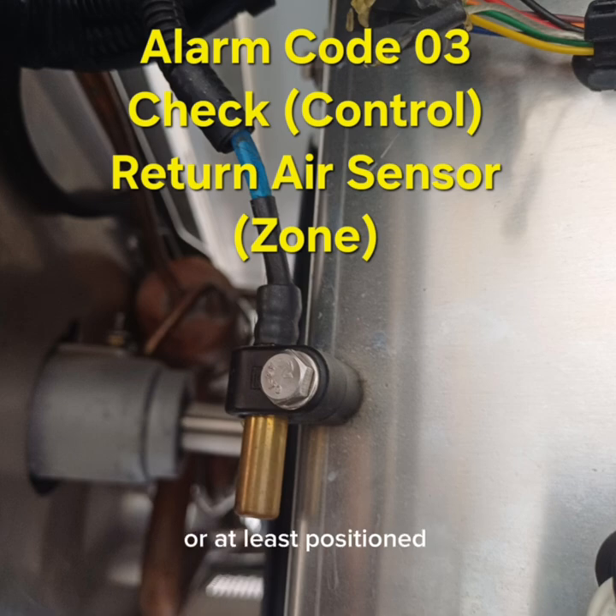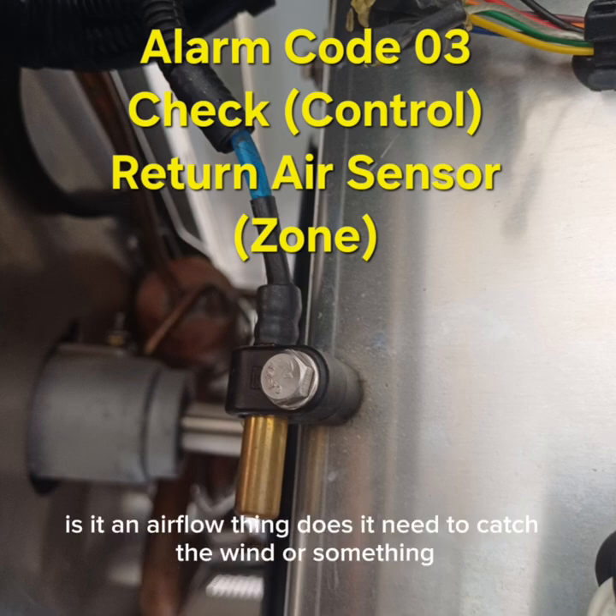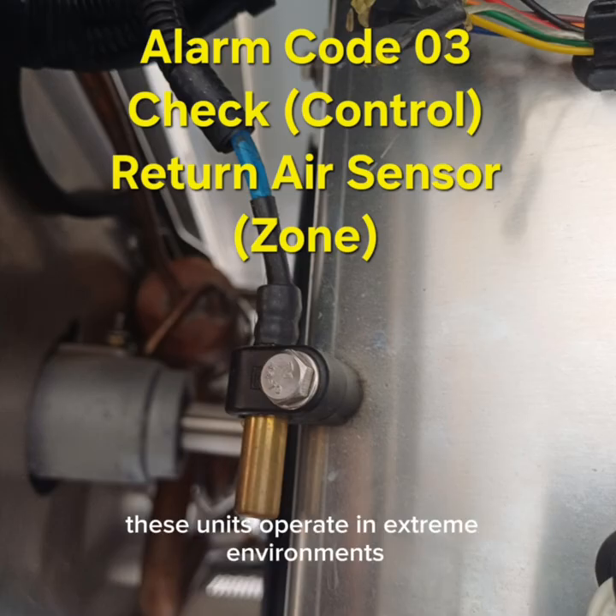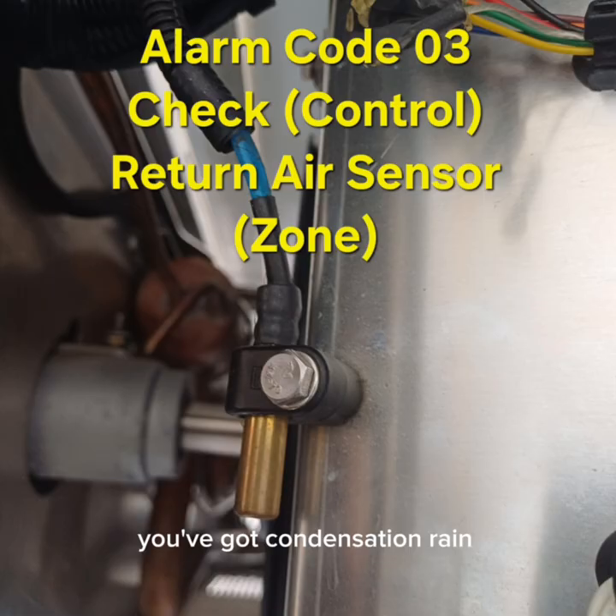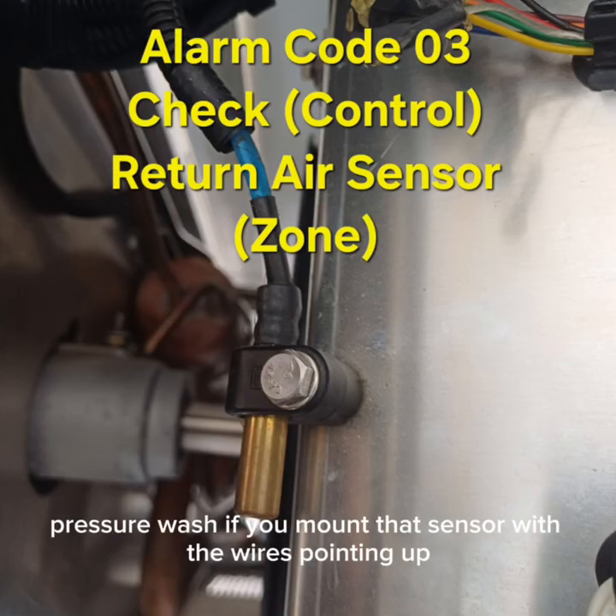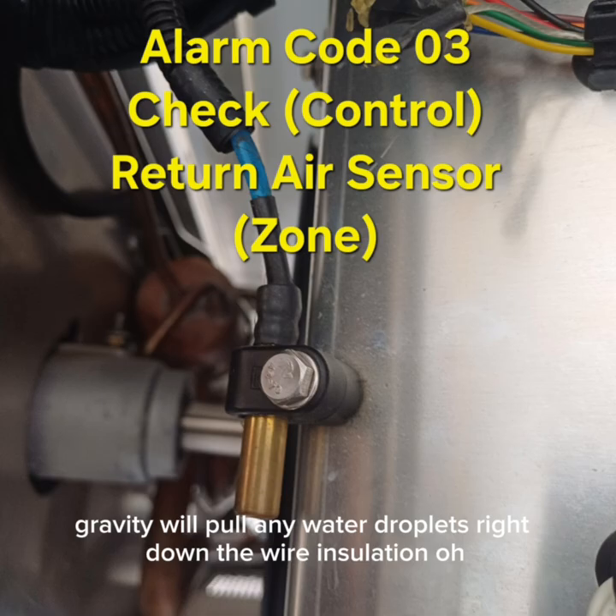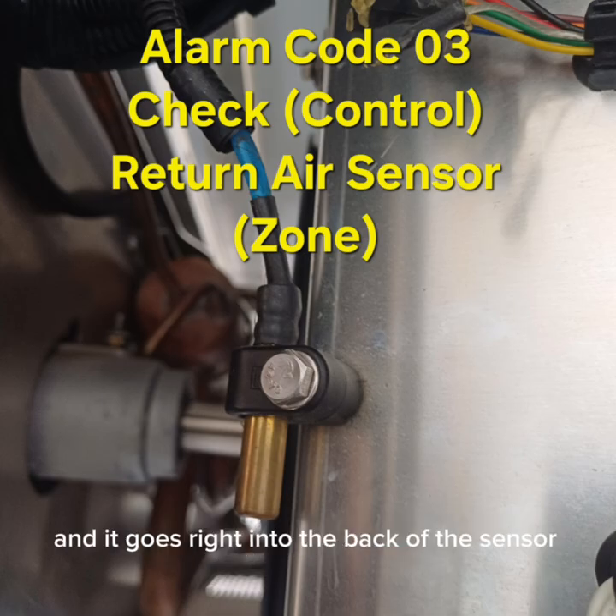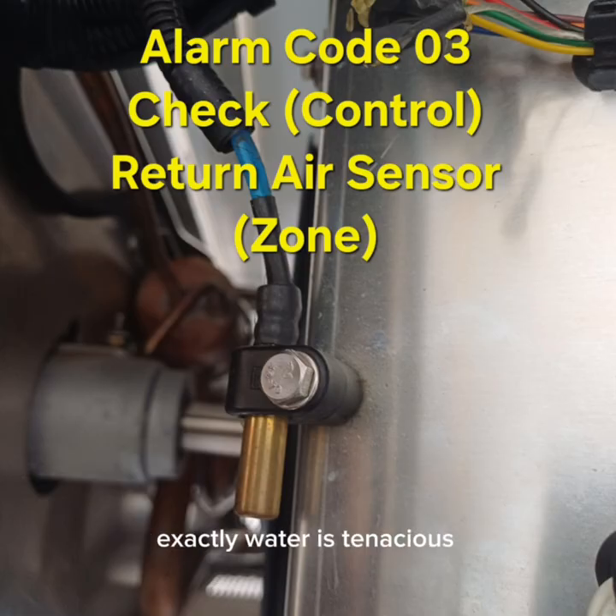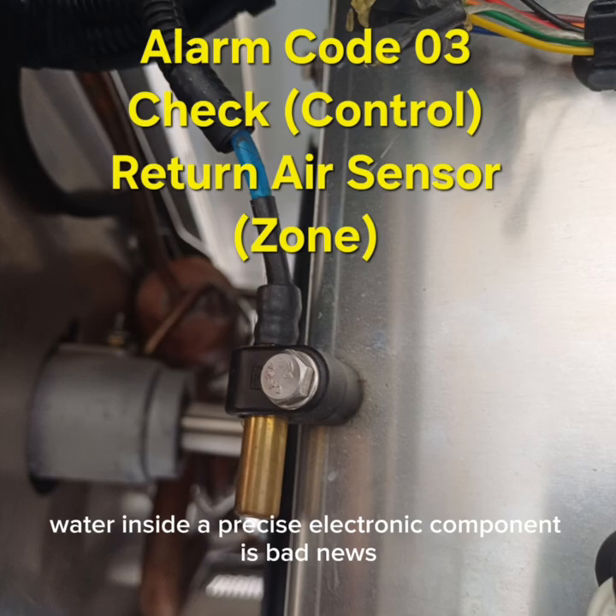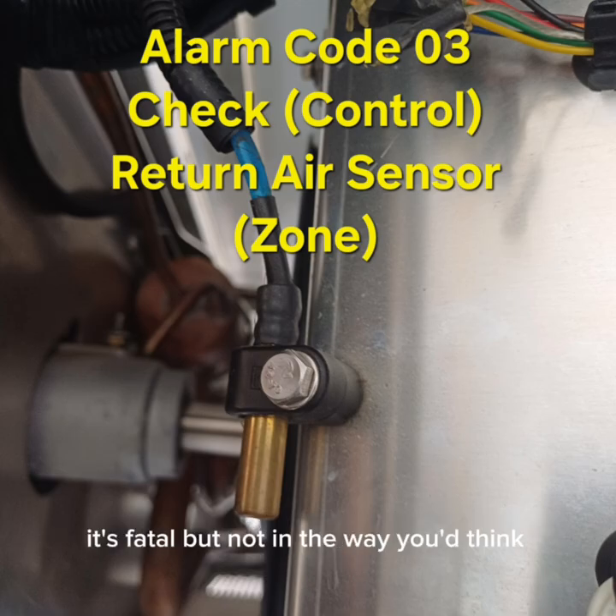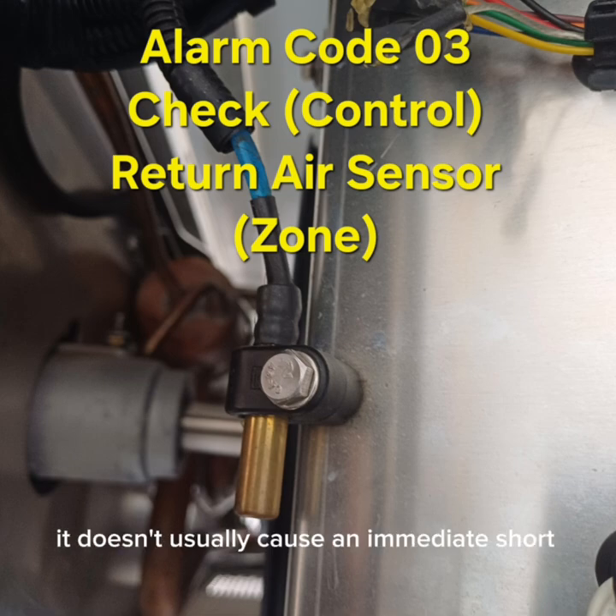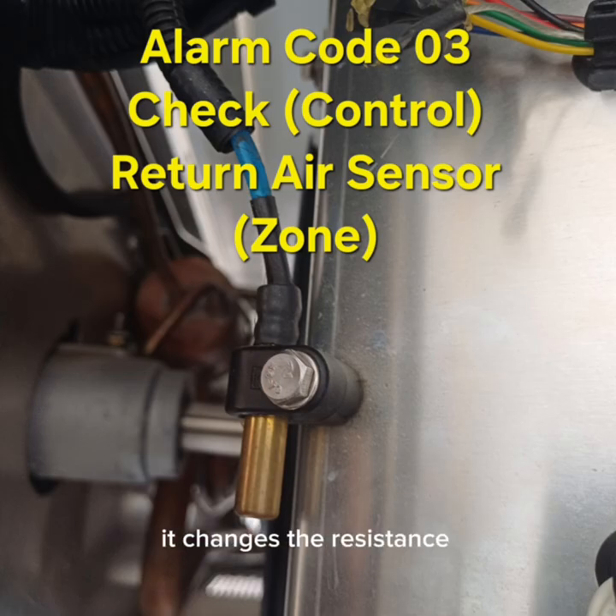Yeah. You want that pointing up, or at least positioned so that the wires coming out of the back of it are pointing down. Why? Is it an airflow thing? Does it need to catch the wind or something? It's a gravity and capillary action thing. These units operate in extreme environments. You've got condensation, rain, pressure washing. If you mount that sensor with the wires pointing up, gravity will pull any water droplets right down the wire insulation. Oh, and it goes right into the back of the sensor. Exactly. Water is tenacious. It will wick its way right inside that shell. And I'm guessing water inside a precise electronic component is bad news. It's fatal, but not in the way you'd think. It doesn't usually cause an immediate short. It causes the readings to drift. It corrodes the element slowly. It changes the resistance.